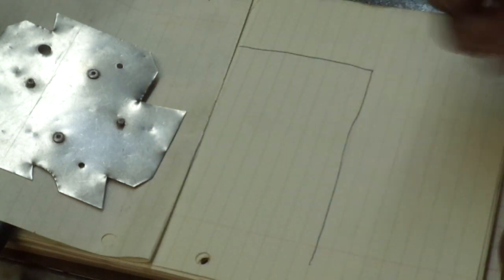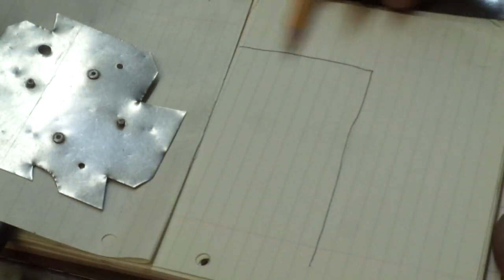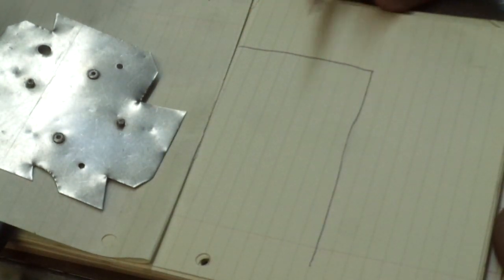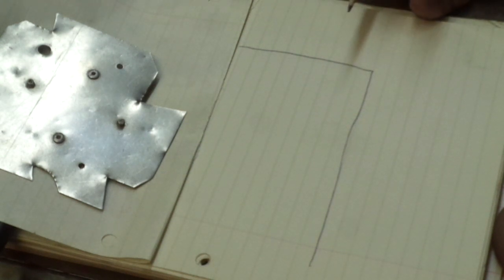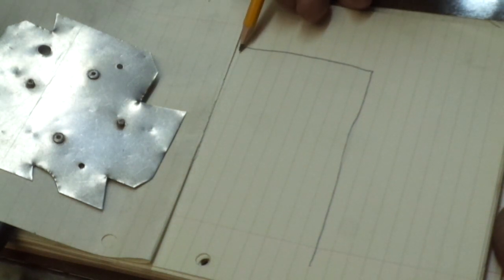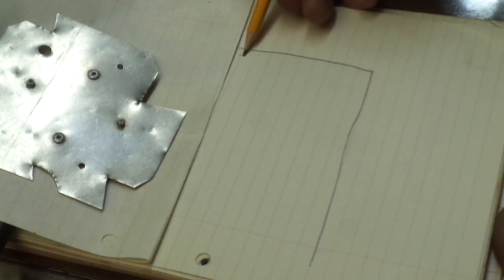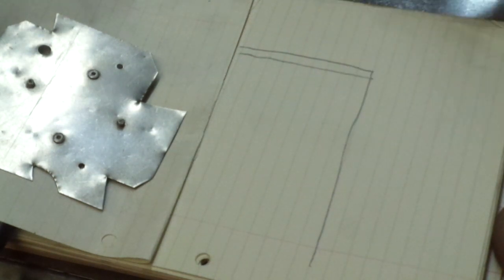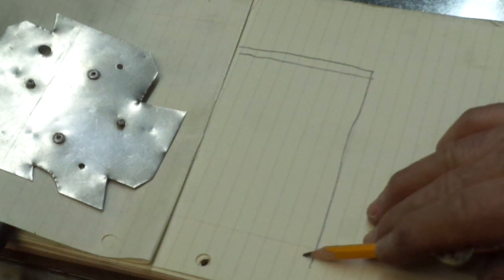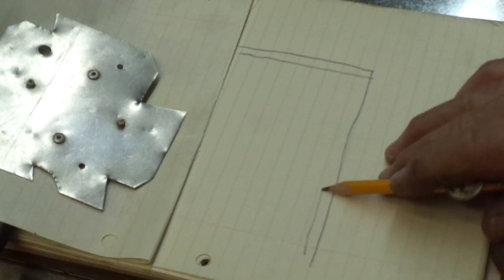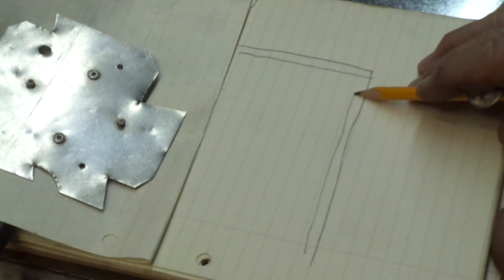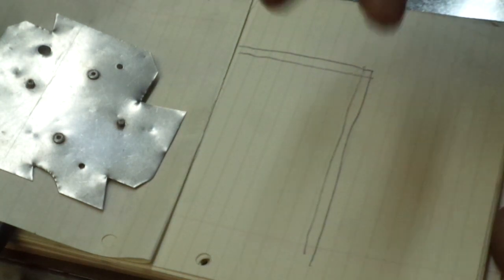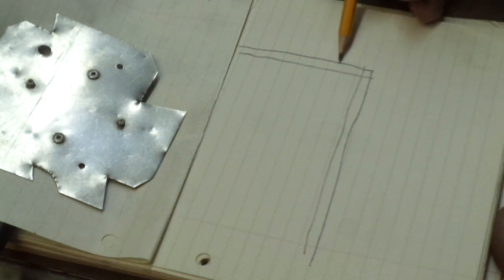Now, in laying out the auxiliary drain pan, you're going to have four corners to that pan. So what I've done, for clarification, is draw just one of the corners on the paper. We know we want a half-inch safety hem on it, so it doesn't cut your fingers. So we're going to make a half-inch scribe down all four corners, all the way around the perimeter of the cut size of the piece of metal. So there's a half-inch. We want this to be a half-inch deep, this particular one. So now you've got a half.